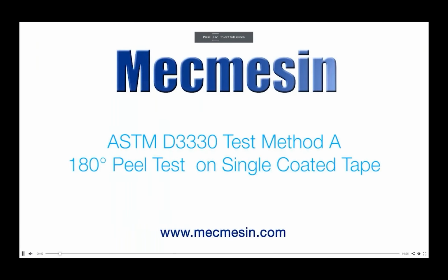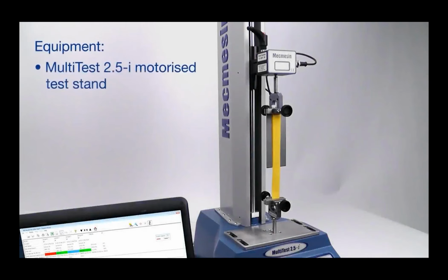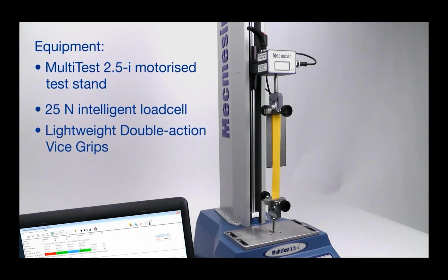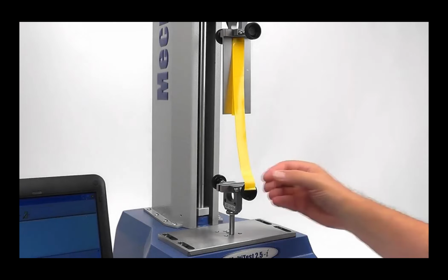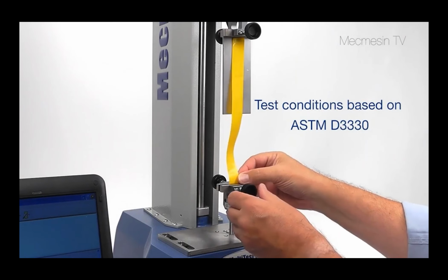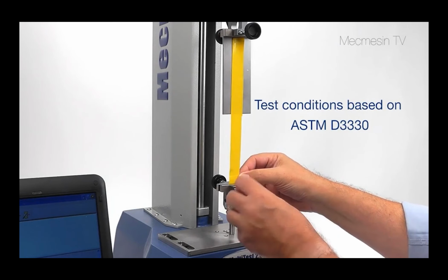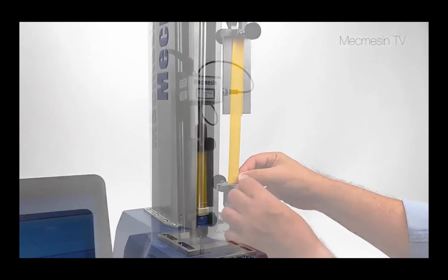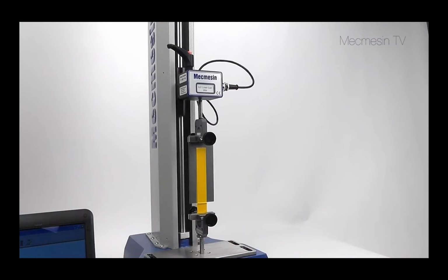So this short video shows a force test stand and software performing a 180-degree peel test based on that D3330 standard. The control software can be programmed to calculate the average peel force over the required sample length and can report the force per unit width of tape.